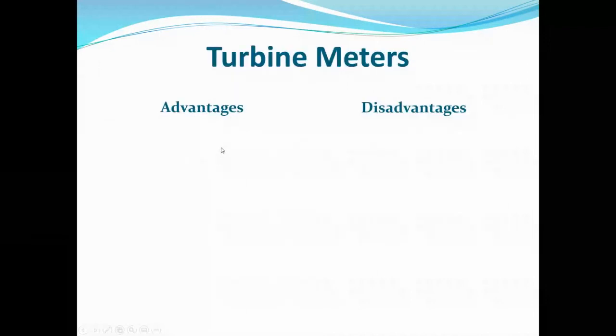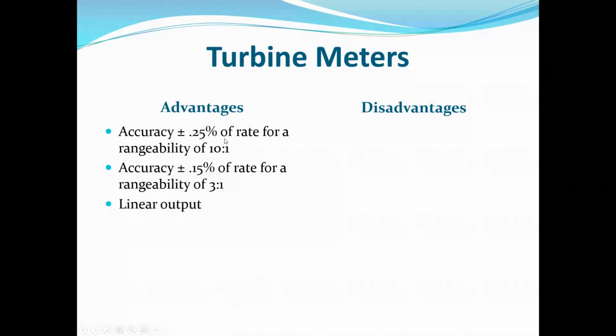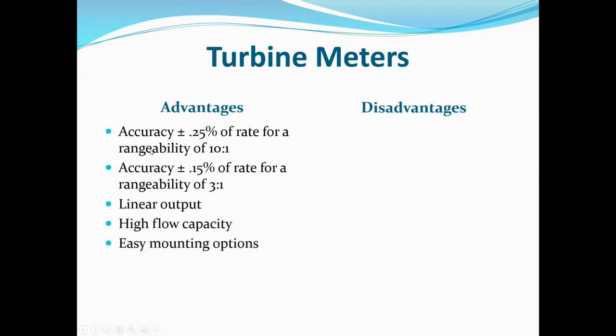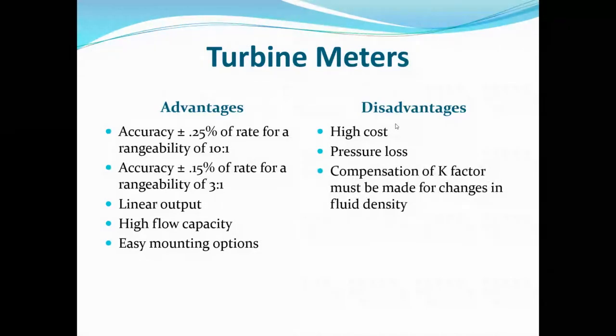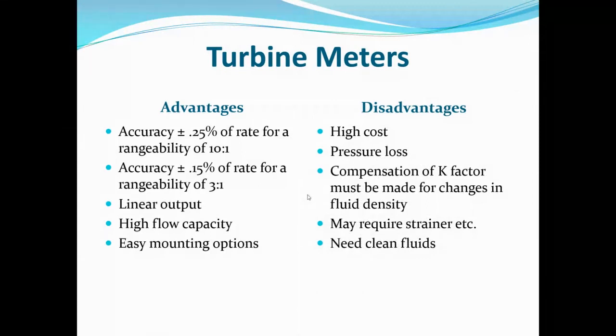Advantages of turbine meters: accuracy of about 0.25%, rangeability of about 10-to-1, linear output, high flow capacity, and easy mounting with many styles available. Disadvantages: they are expensive — a half-inch unit can be $600-$800. High pressure loss because they impede the flow stream. K-factor compensation must be made for changes in fluid density or wear. Strainers may be required due to the need for clean fluids.